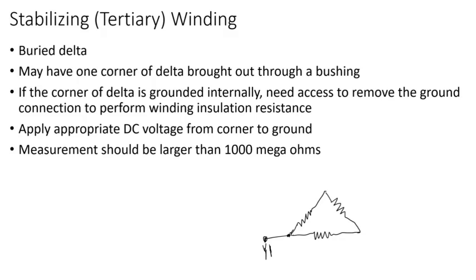In this video I'll talk about stabilizing winding insulation resistance, sometimes referred to as tertiary. This winding is not connected to load, typically a buried delta connected with all terminals not brought out except one brought out for grounding purposes. May have one corner of the delta brought out through a bushing.